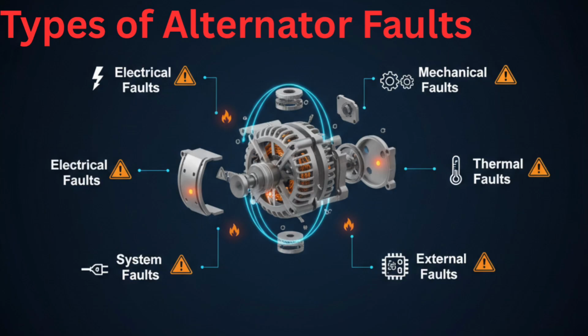Types of alternator faults. In this slide, you see an exploded 3D view of the alternator with different fault zones highlighted. Alternator faults can be classified into 5 main categories: electrical, mechanical, thermal, system, and external faults. Electrical faults include short circuits, overload, insulation failure, and earth faults.